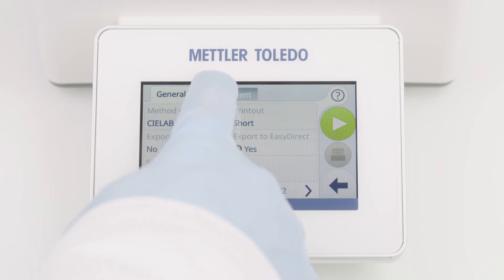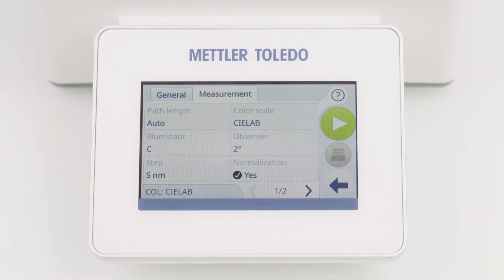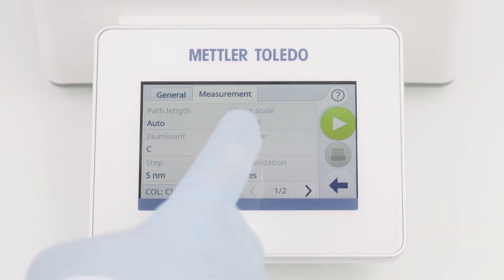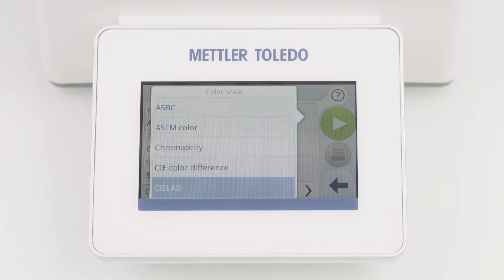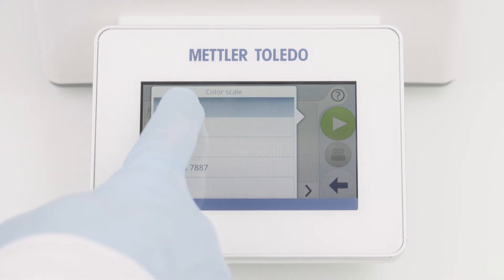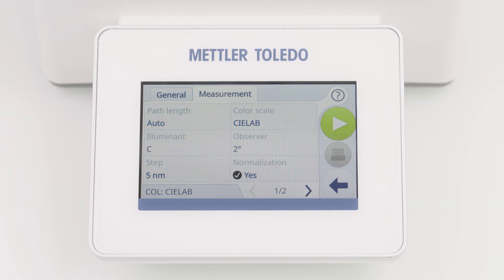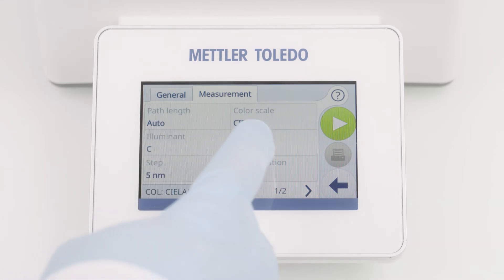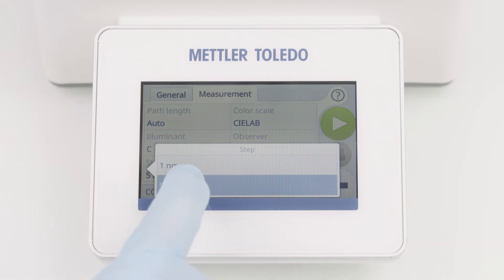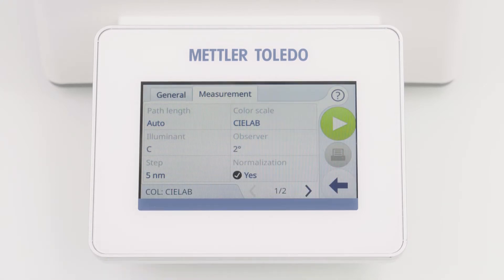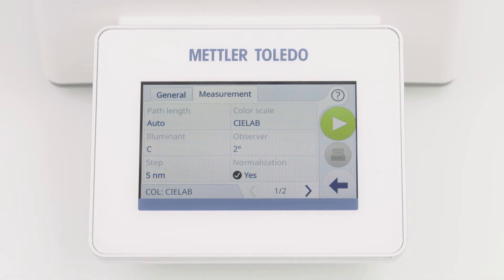The Measurement tab contains all measurement information. You can define the path length and choose a color scale from the list, for example CIELAB color. You can choose between different illuminants and observers, and define the step size: one or five nanometers. To follow the official calculation of the 10 millimeter path length, you can use normalization. With this parameter activated, the measured transmittance values are automatically recalculated to this path length.